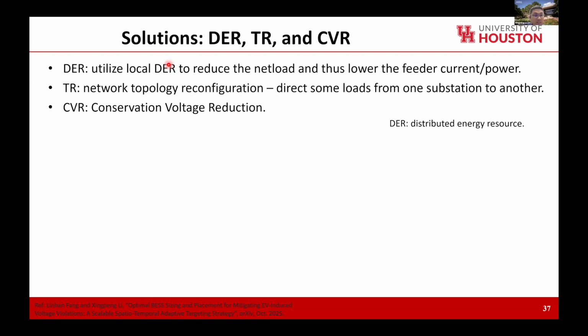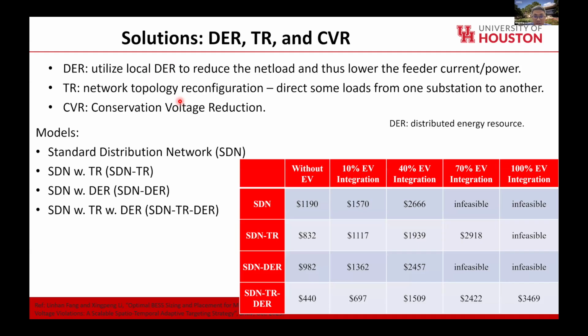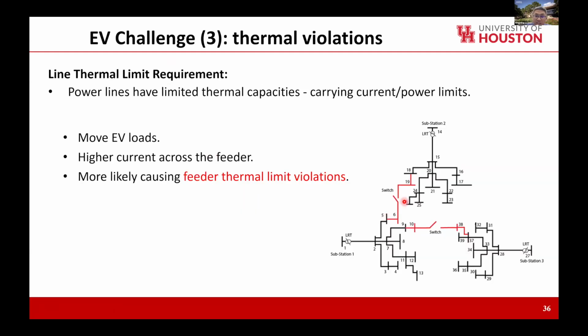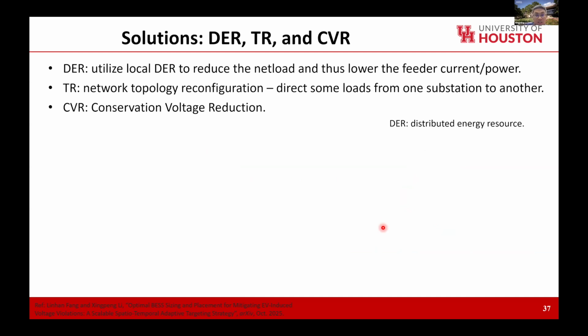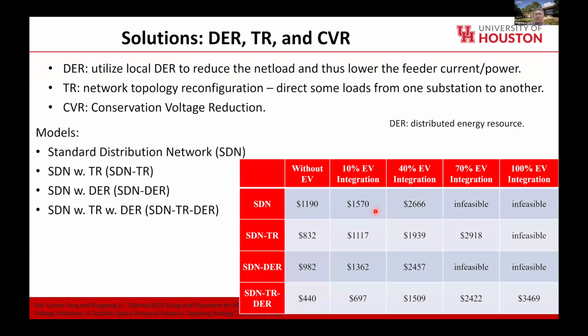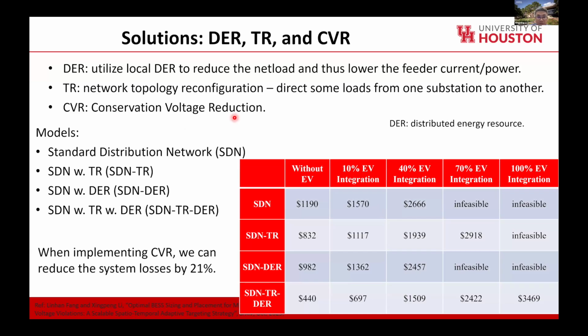A second solution is to optimize the distribution network topology. For example, if a substation area has more loads, maybe we can redirect some loads from this distribution network to another distribution network, so that we have a more evenly distributed electrical demand among multiple nearby substation systems. We did some analysis and showed the benefit. The third strategy could be to purposely reduce the voltage magnitude at the substation level. This is also an industry practice. If we implement this strategy, we may be able to reduce the losses by 21%.